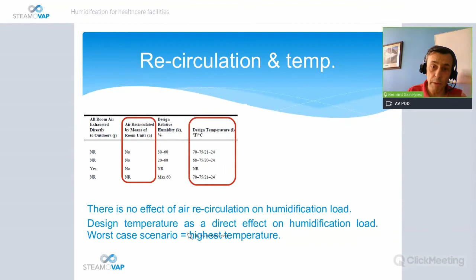So let's look at the different humidification methods now for healthcare. We know now that steam is accepted and adiabatic high pressure water atomizing. They have been very, very specific on adiabatic. On steam, we have a choice of electrode boiler, resistive heater, IR, gas-fired humidifier, which we don't do, live steam, ILS, or steam exchange, ISE. And on the adiabatic high pressure water atomizing, they mention a high pressure pump, which we don't do, but if you have a big project, we are able to get it for you. And compressed air and water, which we have.